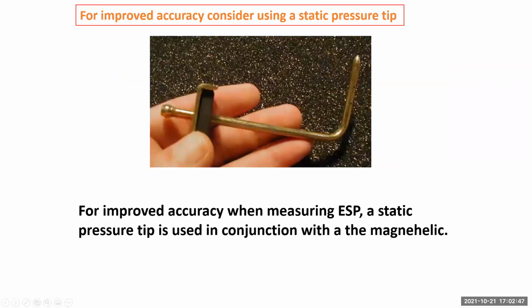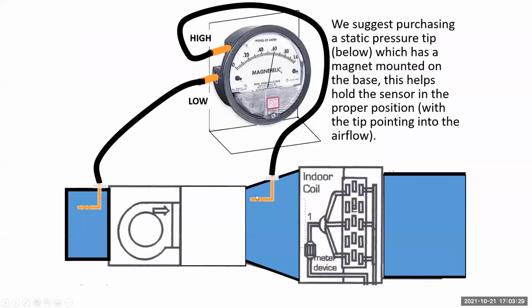You will need this. Pitot tips. Earlier, Craig was talking, have the right tools for the right job. Pitot tips are pretty much a necessity, especially for as critical as airflow and static pressures and everything. Pitot tips are not going to lead you wrong. It's not real long, 5 inches or so, kicks off to a 90. It's going to have a magnet on it, so you just stick it right into your ductwork. You don't have to sit there and hold it. It's going to have an arrow on it to show you which direction to have it for your airflow. They're great to have. Right there shows you your pitot tips in use.